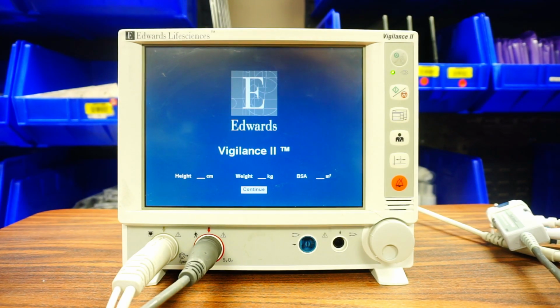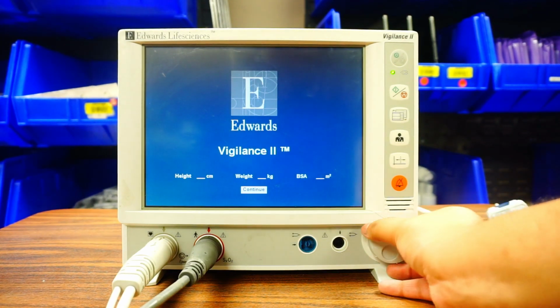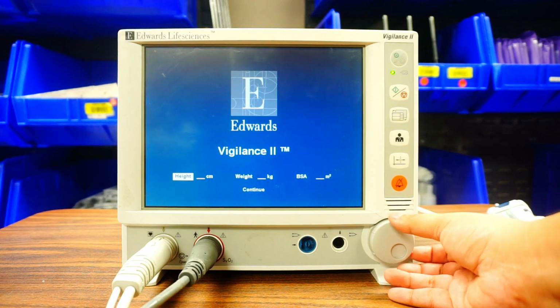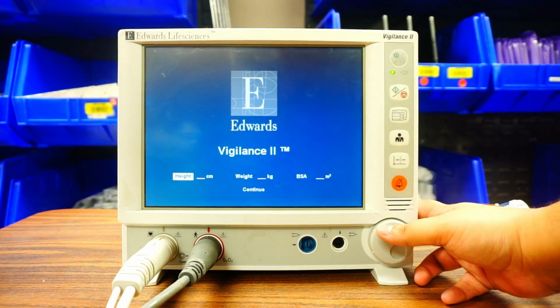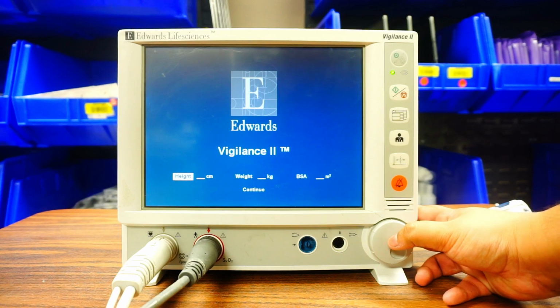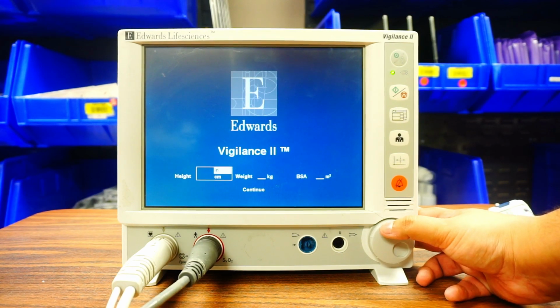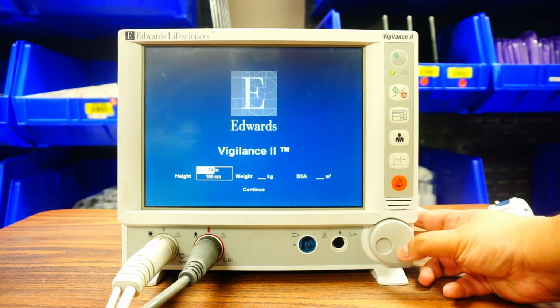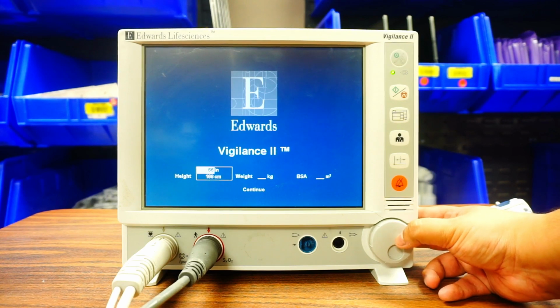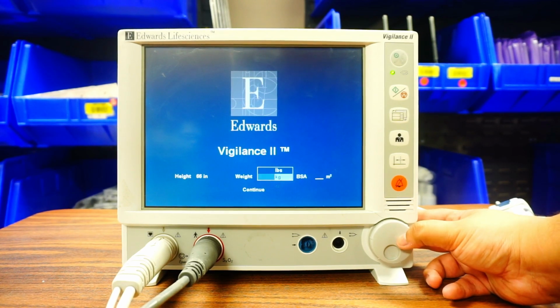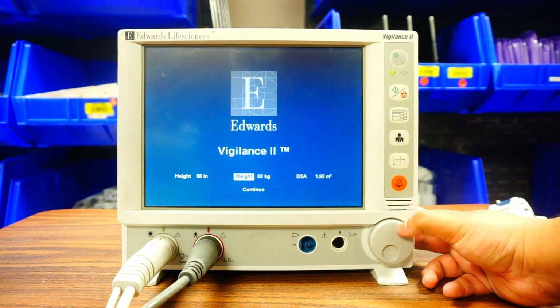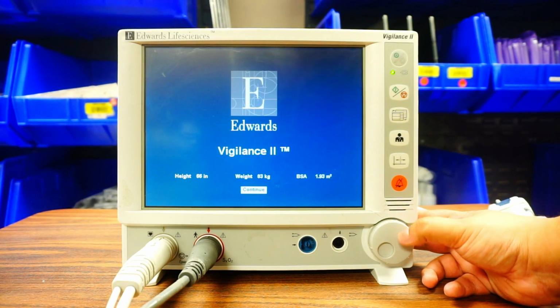Now here with the Vigilance, I'm going to go ahead and set the height and weight of this patient. I do not need to be putting in any other information for this monitor. So to do that, essentially you're going to be using your toggle to go parameter to parameter, and then whenever you have it over that parameter, so on height, I'm going to go ahead and click it. Now I can choose between inches and centimeters. I'm going to go ahead and do inches, and we'll just say the patient is 5'6". I'm going to go over to weight, put my patient's weight in. We'll just say they're 83 kgs. Body surface area will be calculated, and I'm going to press continue.